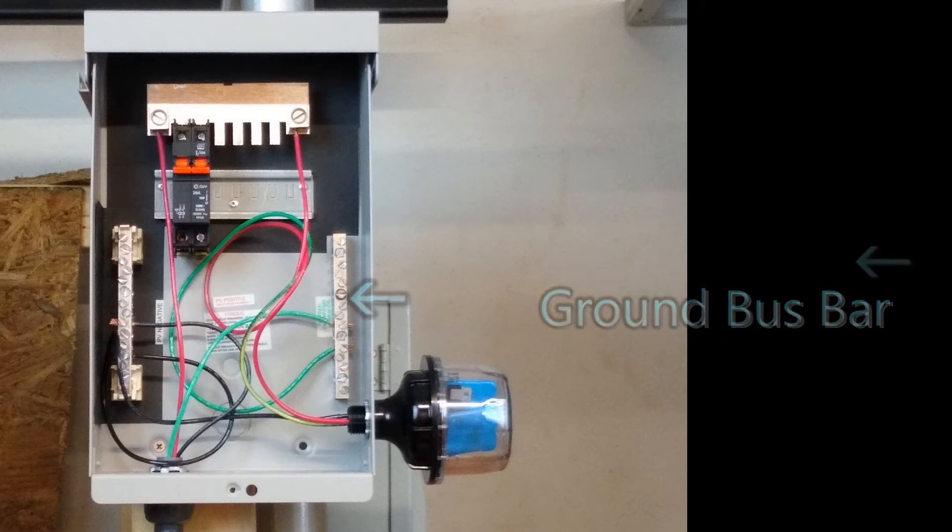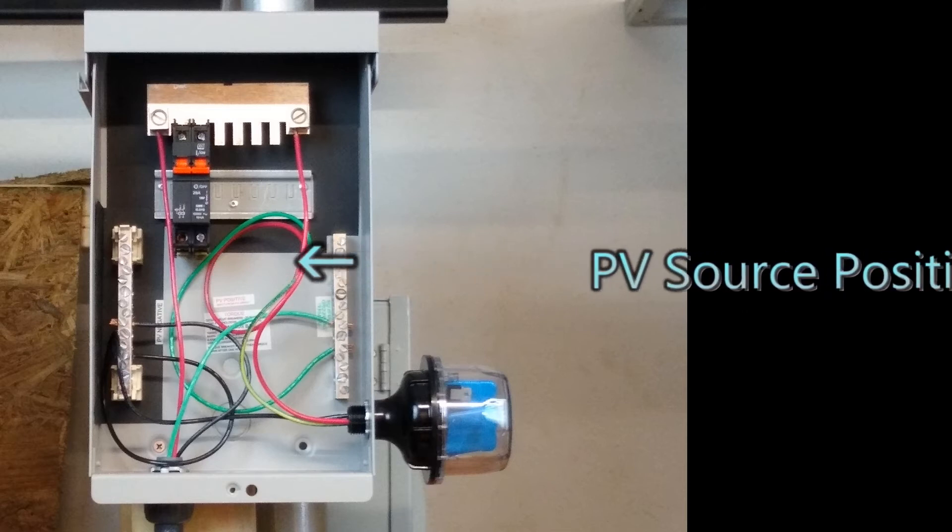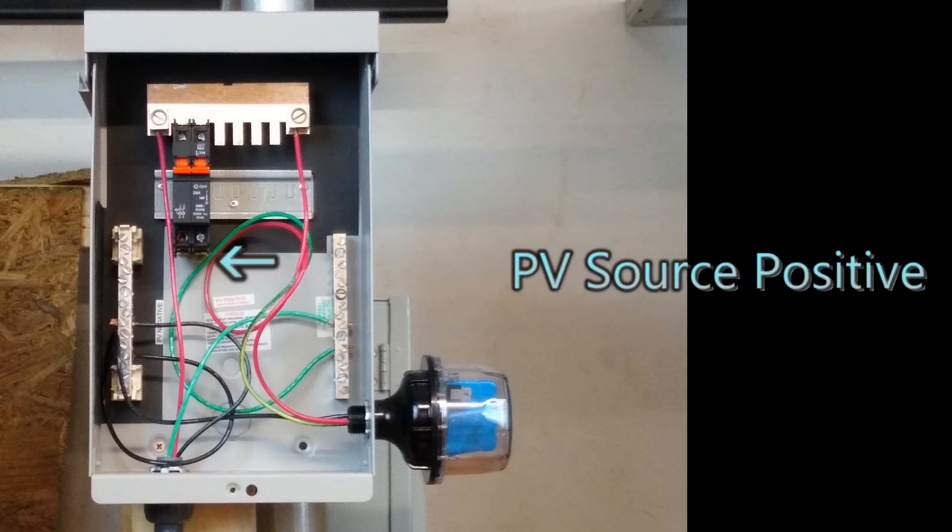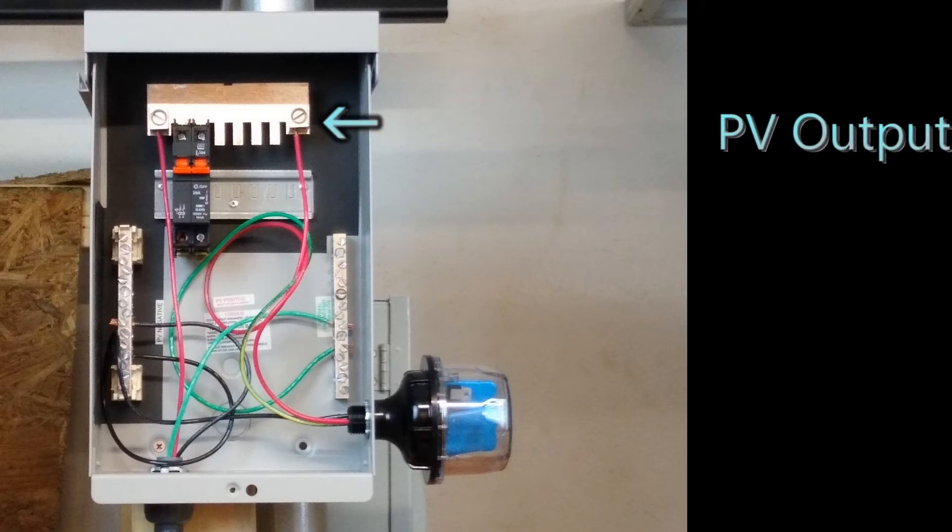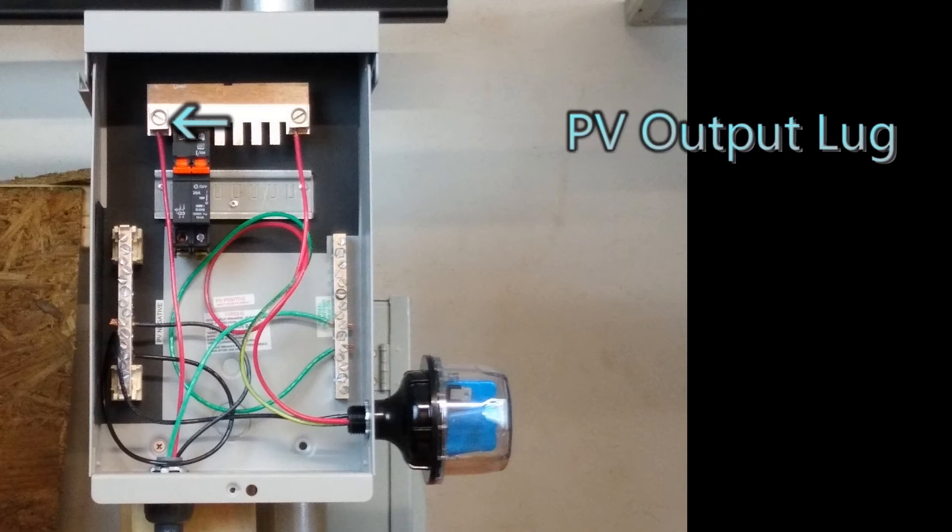You have a ground bus bar where all of the equipment grounding is going to be connected. Then you also have the PV source positives, which feed into the bottom of each of the breakers. Now this particular unit, it can accept up to six strings. There's a PV output lug, which will take all of those six strings and combine the current for an output positive circuit.